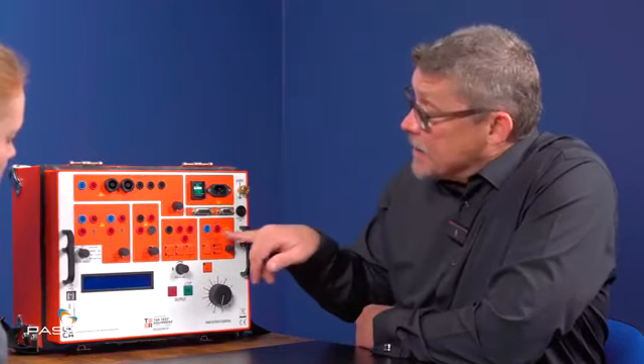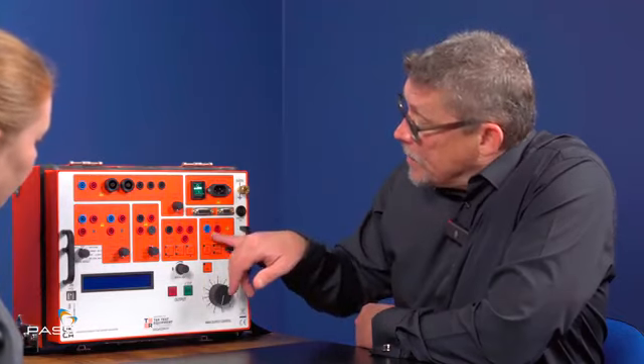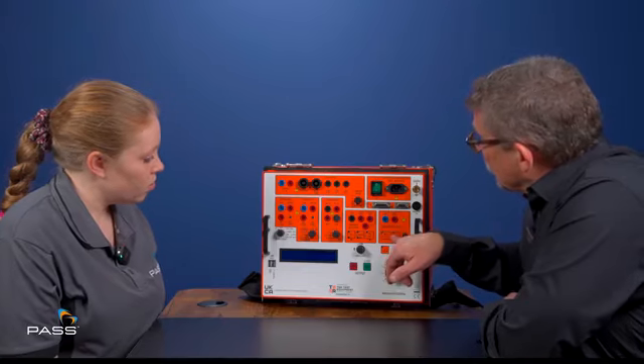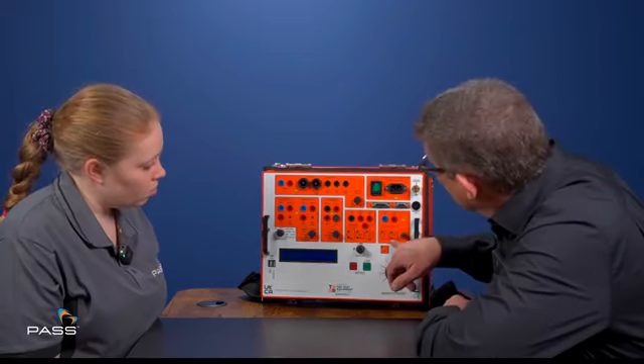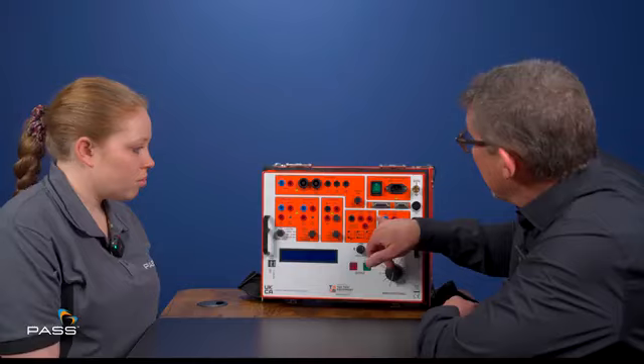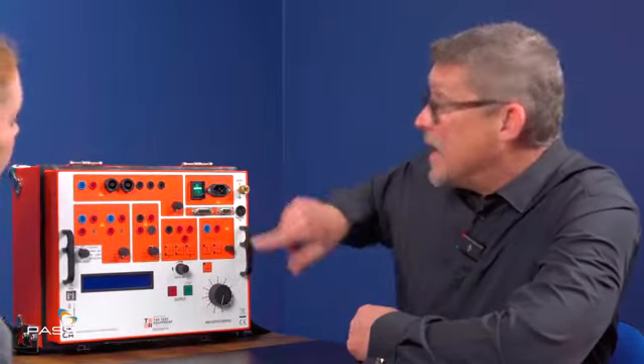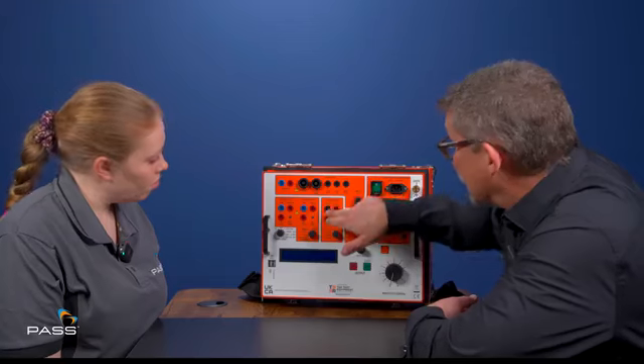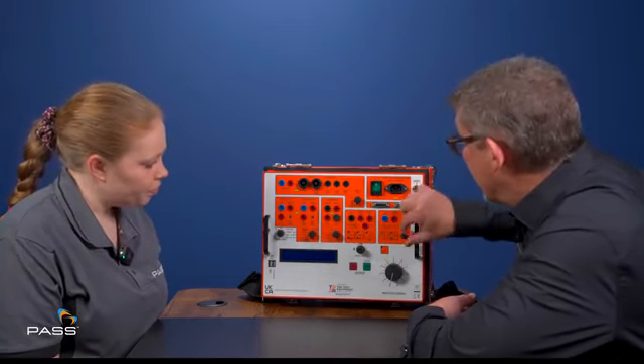When they're fitted to the substation battery, it will give you a DC output that will feed into the relay to power the relay. Simply, this is a battery supply. So it's DC, and we have two ranges, 0 to 220 or 0 to 100, 0 to 60 and 0 to 220. And then we can control the output there. Effectively, once I set that, it's set. So if you've got a unit that requires a 24 volt supply, to meter it, I'll put it into there. I'll come back to that in a minute, but we'd meter it in there, set that, turn it on, and that then becomes our battery supply for the equipment that we're testing.